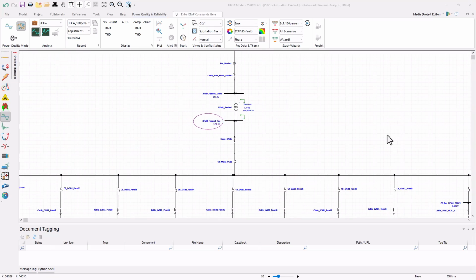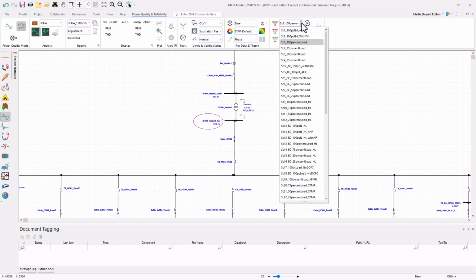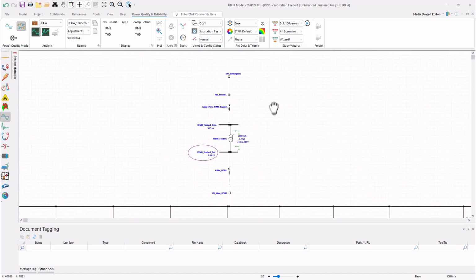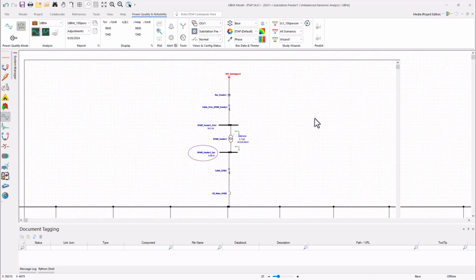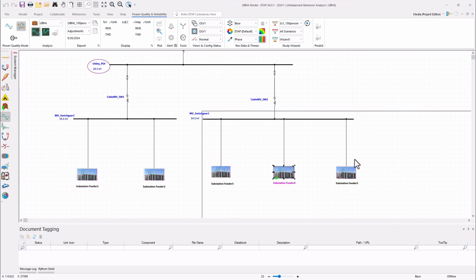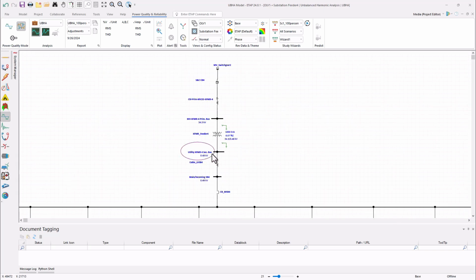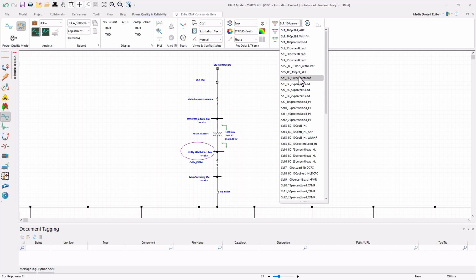So now with this available information, let's try to run the scenarios. We have one of those scenarios where harmonic voltage or current distortions are exceeding the limits provided in the standard. So the one that we're going for right now is scenario 5 BC 100% load, where we could see exceeding distortions in substation feeder 4. So before running the study, let's move out of this composite and move into substation feeder 4. And we're evaluating the results at this transformer secondary bus and service entrance cable here. So let me go and run the scenario.